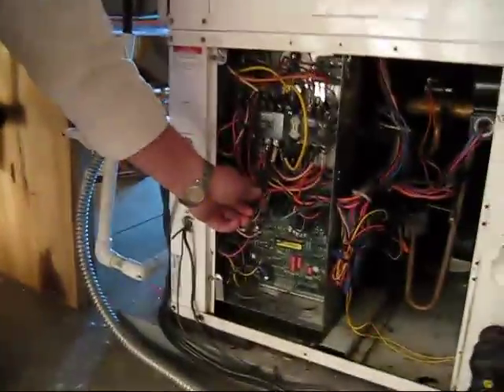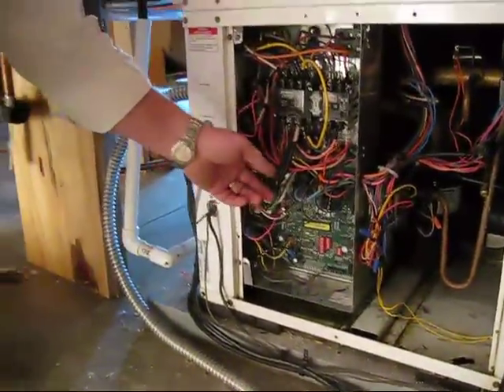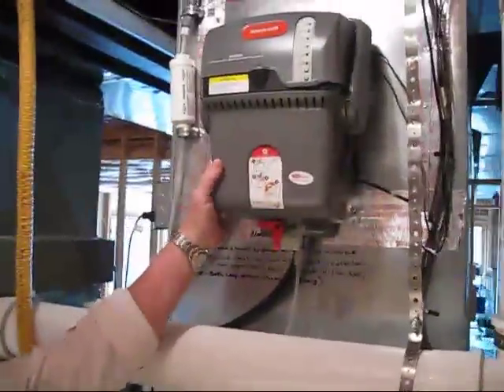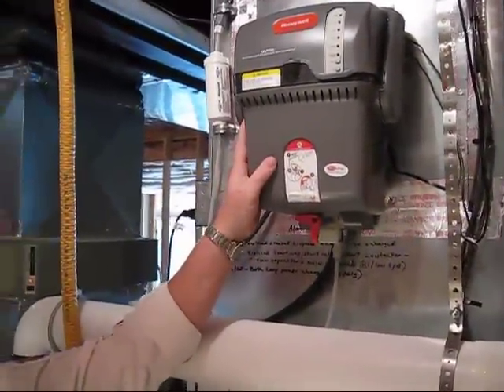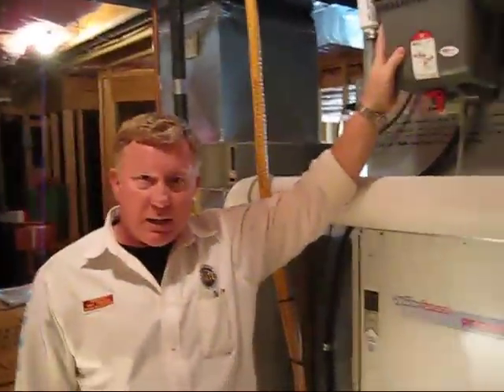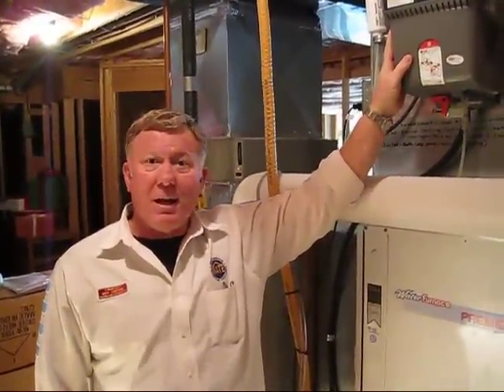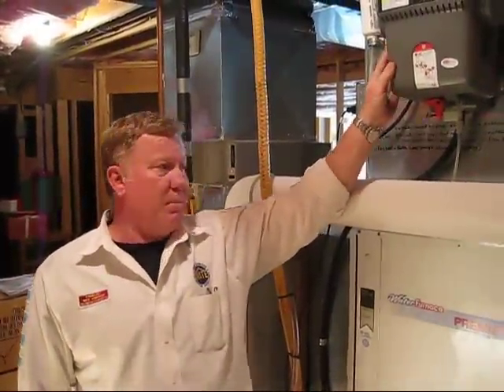Electrical connections need to be checked to make sure they are tight and not loose. Loose connections can burn out circuit boards. It can burn out compressors and or the motors. Whether a system has other accessories, such as this system that has a steam humidifier. This particular humidifier requires other techniques and other procedures in servicing and maintaining it than a bypass humidifier, for example.